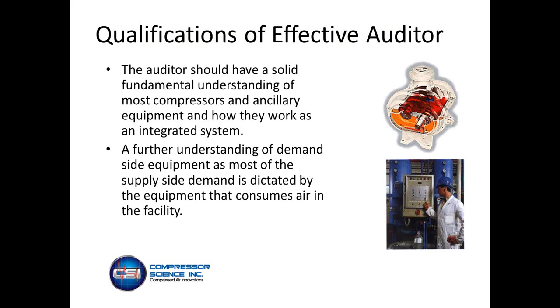Looking at effective auditing, the person who's auditing your facility should have a good fundamental understanding of most types of compressors, because if you're going in to audit a facility, there's different control schemes: modulation, load-unload, variable displacement, reciprocating. They need to understand how those compressors integrate together and with the dryers, the filtration and the piping, and how the demand side of the plant works.